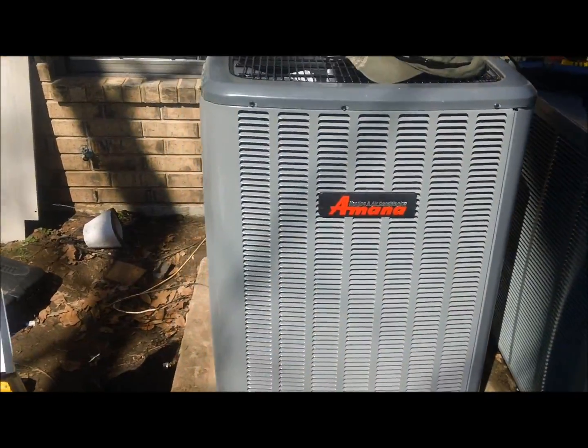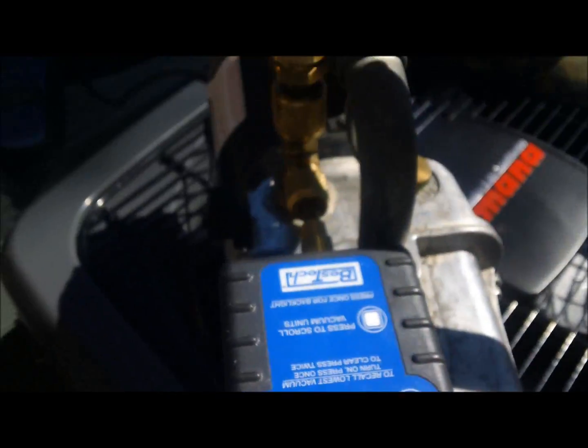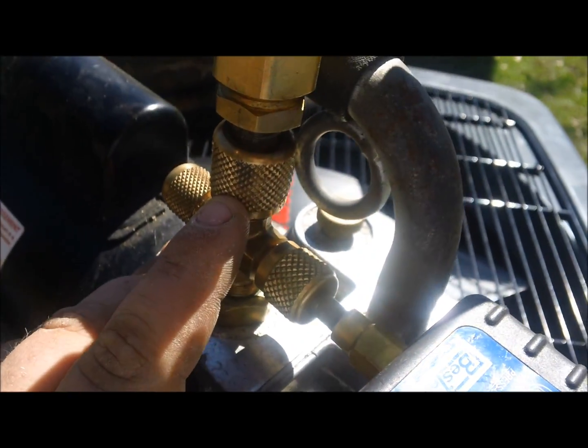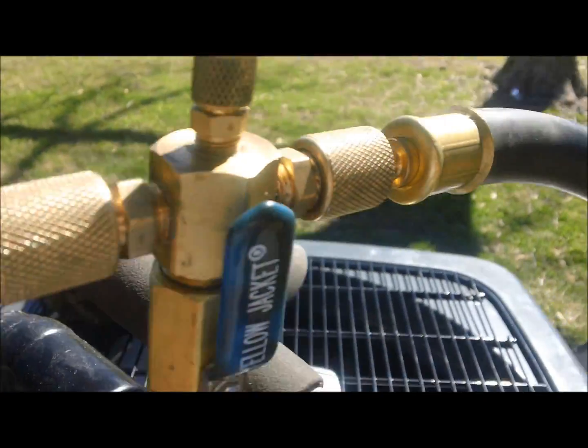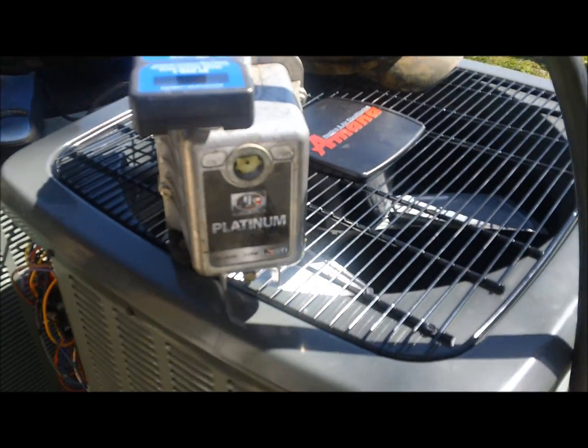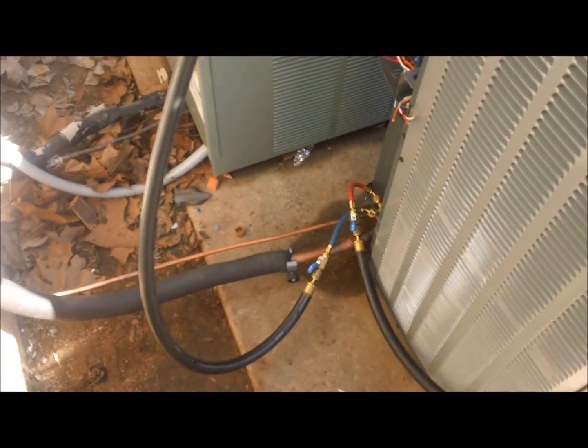The Amana's in the vacuum. We're at 146 microns. Zach, this is what I was telling you — I don't know what happened with my pump, but this fitting here is three-eighths and this one is half inch. I can't hook my hoses here and here like you can — I can hook one here but not here; I still have to use my T. But I got my micron gauge hooked up right here. I don't know, I guess I didn't get as lucky as you on my pump. But it's calibrating and it was at 146, so really happy with the way this job came out.